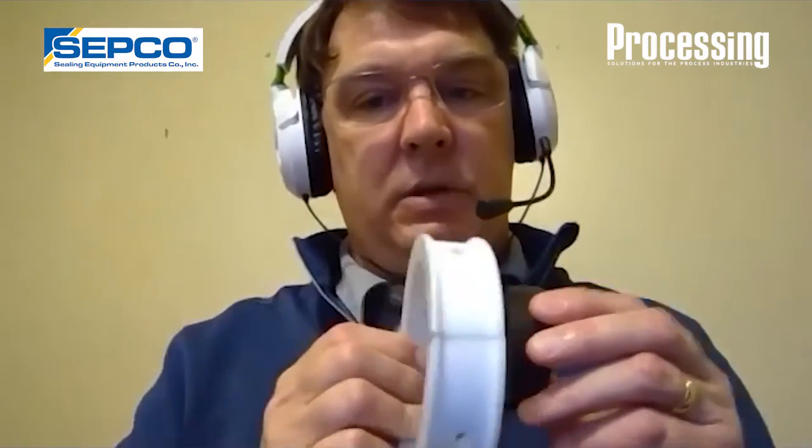And how that works is we have a system of air that comes into the seal that is throttled down, and so that we will not introduce air into the impeller, into the wet end of the pump, through these bushing systems, we create a flush system. On the other side of the seal, we put through the lantern ring a typical flush. And the theory behind it is, with the air seal, we are only sealing the flush of the pump. Hopefully that makes some sense. Instead of sealing, we're letting the flush seal the pump itself. And then the air seal is just sealing the flush.